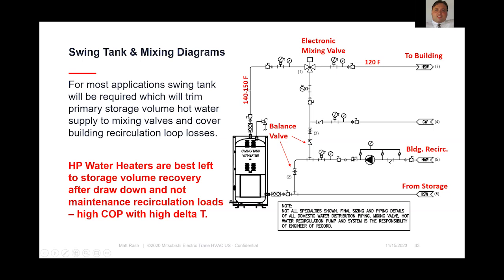So you may be storing at 140 to 150 or hotter, and you're delivering to the building typically at 120. So it's important to store, obviously for bacterial, microbial growth, protection against Legionella. We're storing in our primary storage tanks and in the swing tank, maintaining temperatures typically at 140 or above.